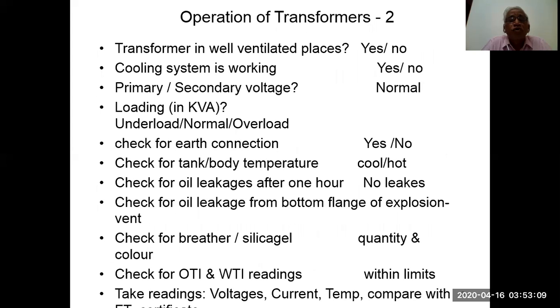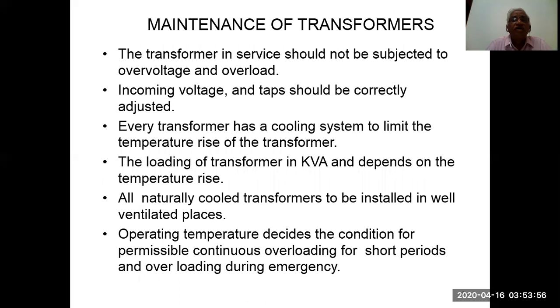Operation of transformer 2. Transformers in a well ventilated place, yes or no. Cooling system is working, yes or no. Primary secondary voltage normal. Loading in kVA, underload, normal load or overload. Check for earth connection, yes or no. Check for tank body temperature. Check for oil leakage after 1 hour. Check for oil leakage from the bottom flange of explosion vent. Check for breather and silica gel quantity and color. Check for OTI, WTI readings within the limits, and take readings of voltage, current, temperature, compare with the results you already have, the FAT as well as the previous readings.